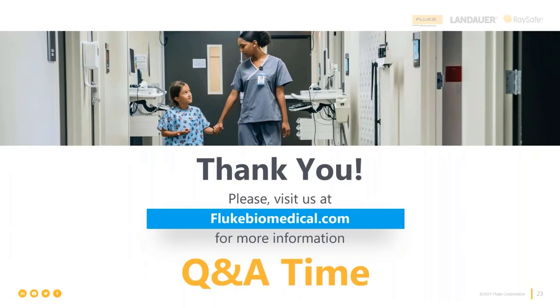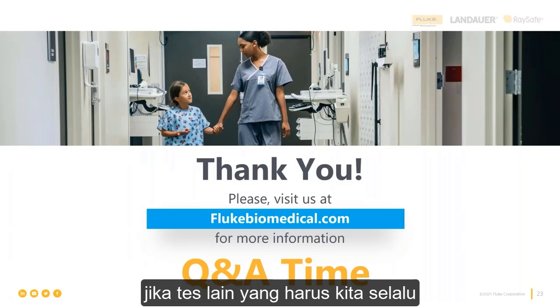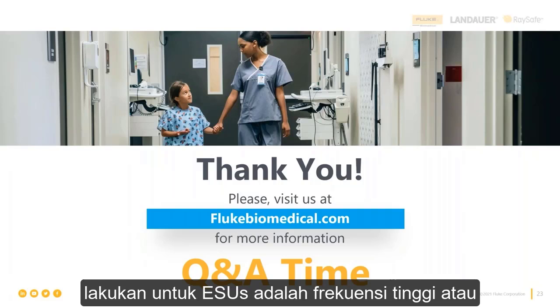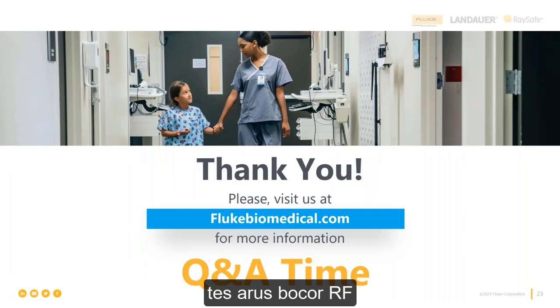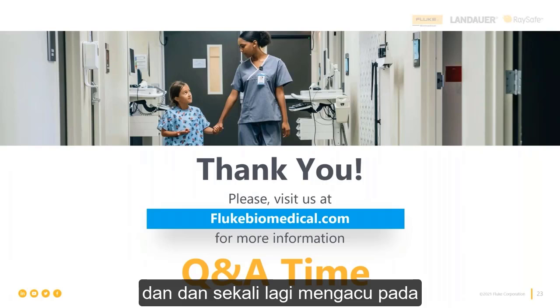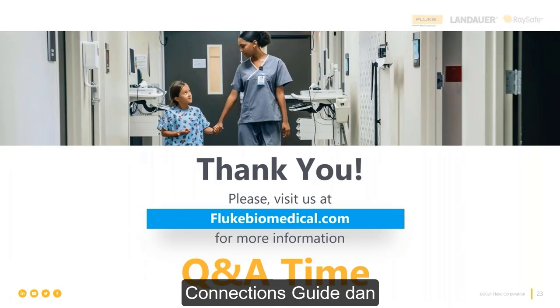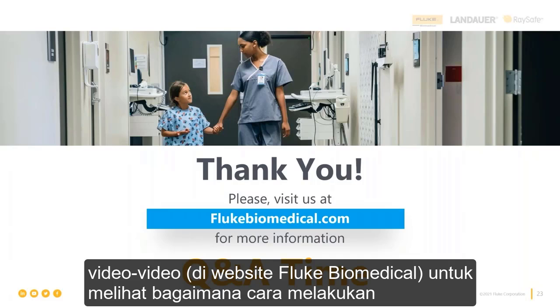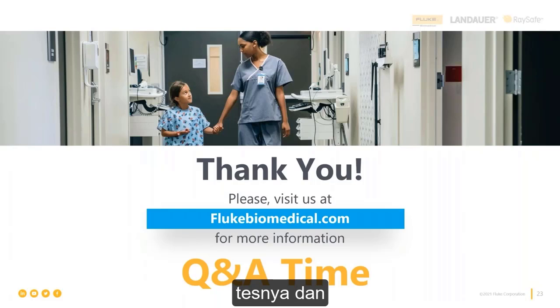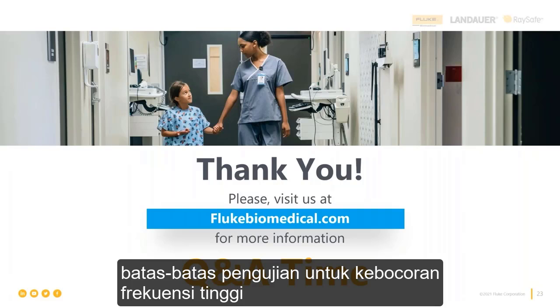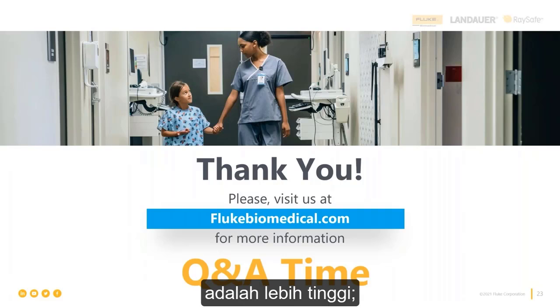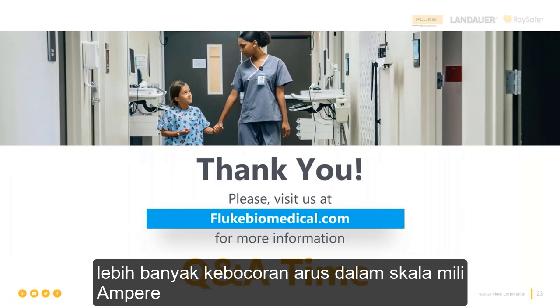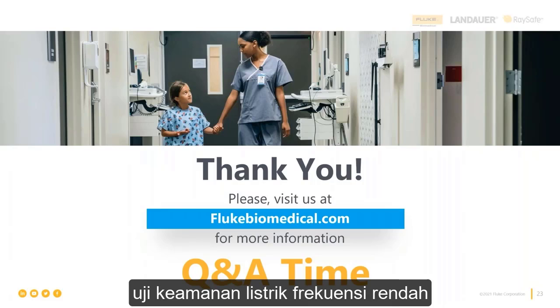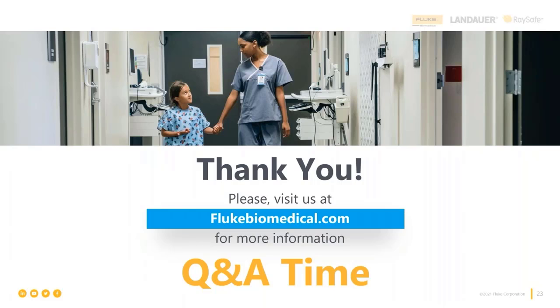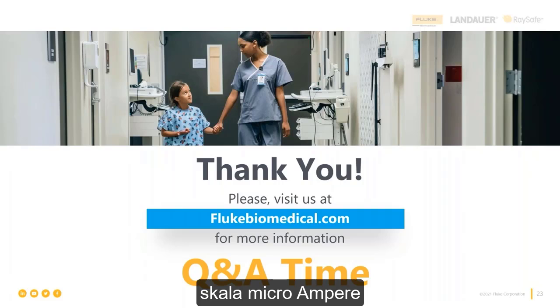The other test we must always do for ESUs is the high frequency, or RF, leakage current test. Refer to the connections guide and the videos in order to see how to do that test. The testing limits for high frequency leakage are higher—it allows more leakage current, in the milliamp range, compared to the standard low frequency electrical safety test, which is in the microamp range.